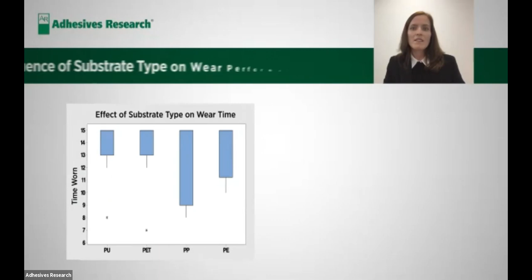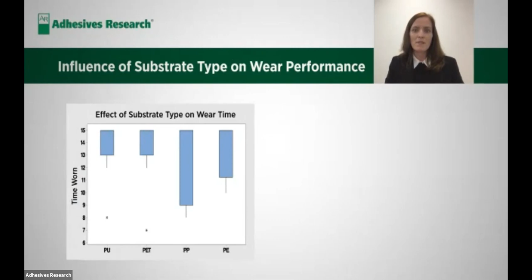Another contributing factor here was the fact that there were so many different devices worn, increasing the probability that they'd knock against each other and contributing to fall-offs. The substrate type can also influence wear performance. Here we see the results of a wear study performed with 4 different substrates: polyurethane, polyester, polypropylene, and polyethylene. The time worn is illustrated in the box plot. As can be observed, the polyurethane and polyester samples performed most favourably, in contrast to the polyethylene and the polypropylene samples.